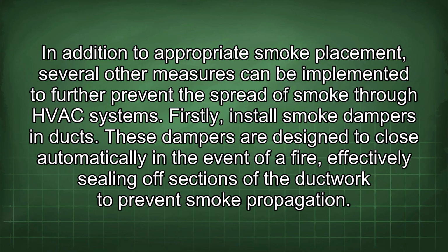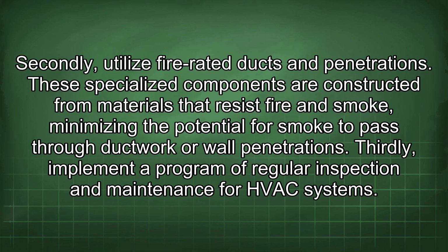In addition to appropriate smoke placement, several other measures can be implemented to further prevent the spread of smoke through HVAC systems. Firstly, install smoke dampers in ducts. These dampers are designed to close automatically in the event of a fire, effectively sealing off sections of the ductwork to prevent smoke propagation. Secondly, utilize fire-rated ducts and penetrations.